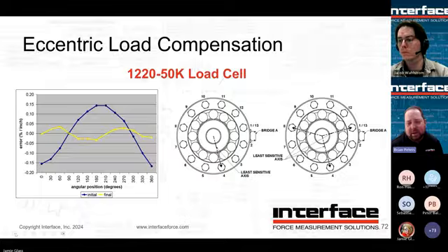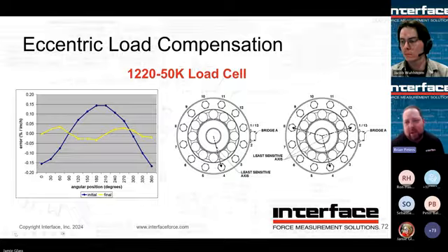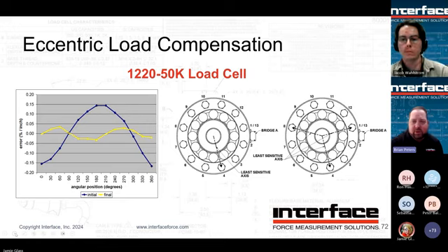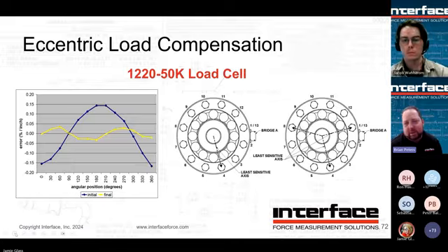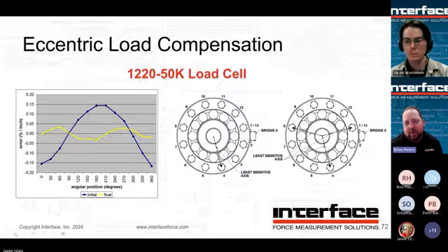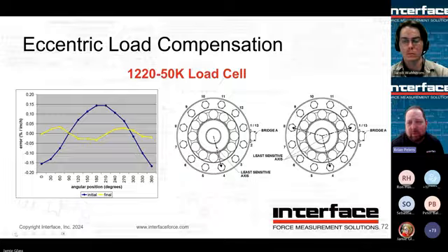Even if you have, let's say, a long horizontal load string run, you got actuators hanging off of things. Again, sometimes even with support, you still can't quite neutralize. An LP is not going to care in most cases. And we have some customers that really want to know where the neutral axis is, and because we have full traceability during the manufacturing process, we can actually provide a chart similar to the one on the right there that says here, based on the connector, this is where you want to orient those side loads if you can't reduce them. So again, this is something we do on every single low profile, and we make more of these than anybody else in the world. So just a little bit of special that makes these perform better.